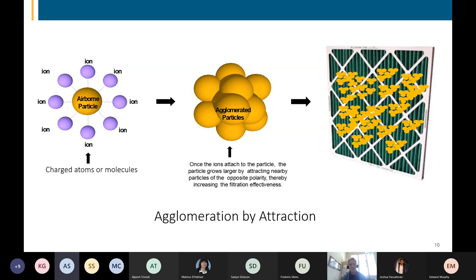Very first job I ever did in the industry in 1982, when I went to work for Carrier, was a clean room application where we did a couple of things. Number one, we designed the clean room for 200 air changes per hour. Think of that, 200. Think of the air movement and the velocities associated with 200 air changes per hour. I can more effectively propel smaller particles at higher velocities as well. We installed ULPA filtration. I think that was 99.99997% efficient, right? So I increased air exchanges and air movement to help better transport smaller particles.